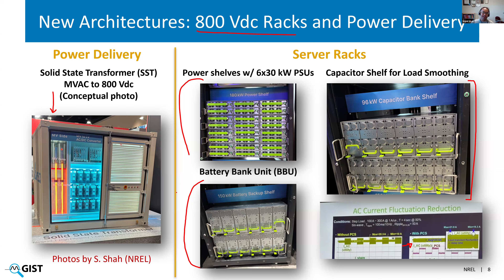We talked a lot about the load profiles or the load fluctuations. And there is this new development, the capacitor bank unit, CBU, which again goes inside the IT rack. Its main function is to smooth out the input current. Basically, it absorbs all the load variations at the IT rack level itself so that it doesn't impact the grid. These new developments are led by the front runners of AI companies. They are not, of course, going to be adopted universally, but we have to be mindful of that, because if you talk about load fluctuations, there are some solutions not only at the POI side or behind the meter, but within the IT rack itself. So that needs to be considered in the model.